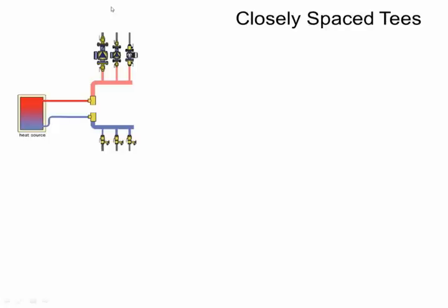Let's say, for example, we have a hydronic system with a heat source, and we have 3 pumps, and these pumps now send heat up to our system, and it comes back. Now, the flow rate of each of these pumps has to go through the boiler. And there's going to be resistance in this boiler. So as this pump turns on, comes back around, and wants to go through the boiler, it's going to create a back pressure against these other pumps because there's resistance in the path ahead of it. Same with these other pumps, they're going to interfere with one another.